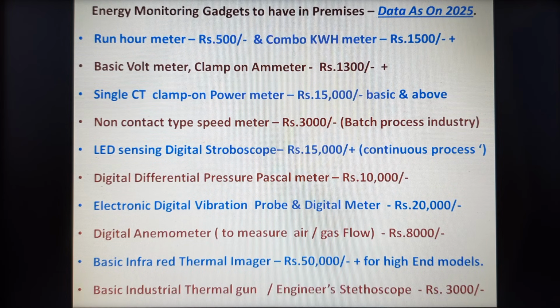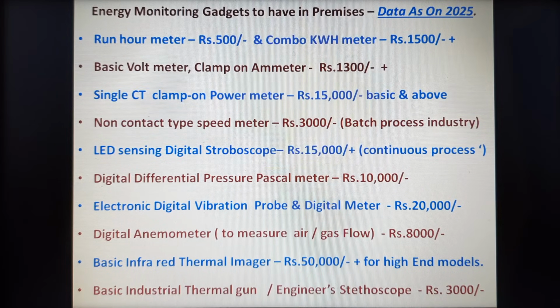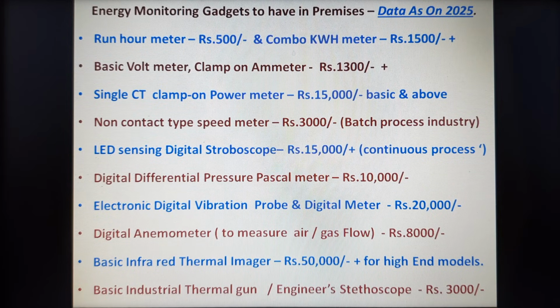The Bureau of Energy Efficiency always says, let us try to monitor the energy consumption, then only can we target the energy reduction in kWh. I am just talking about electricity now. Let us discuss the thermal and other aspects in the next coming bulletins. Any pump or any machine or any motor definitely needs a run hour meter of 500 rupees and a kWh meter of 1500, around 2000 rupees. This can be fitted on each and every production motor, utility motor, auxiliary motor and utility machine.